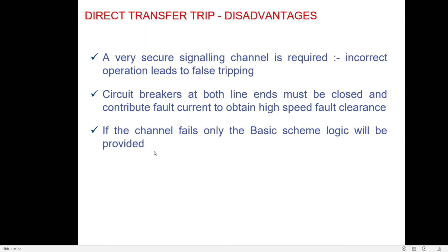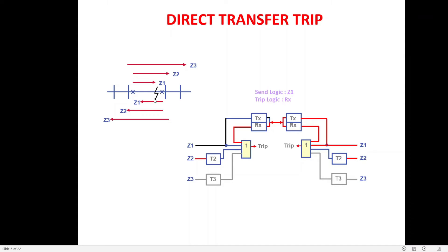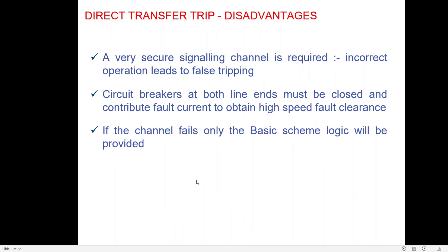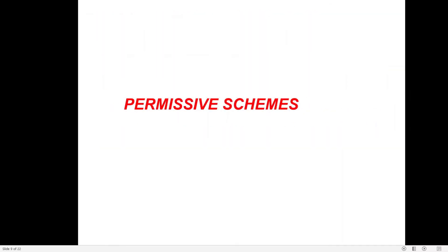The scheme is easy to implement and advantageous for protecting three-terminal lines. The limitations are: a very secure signaling channel is required because incorrect operation leads to false tripping; circuit breakers at both line ends must be closed, since if a breaker is open Zone 1 cannot pick up and no carrier is sent, so tripping at the other end is delayed to Zone 2 timer; and if the channel fails, only basic scheme logic applies.